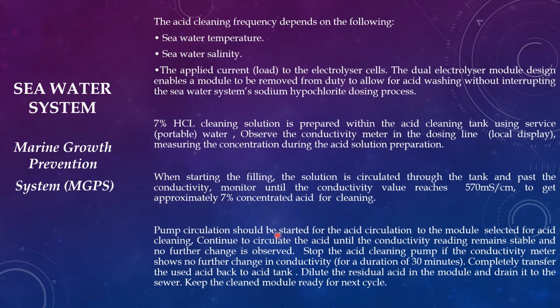Pump circulation should be started, and the 7% acid is ready for circulation to the module selected for acid cleaning. Continue to circulate the acid until the conductivity meter remains stable and no further changes are observed. When you start the circulation, conductivity starts increasing. When it remains stable, stop the acid cleaning pump. The conductivity meter shows no further change in conductivity for a minimum of 30 minutes. If it is stable and conductivity is not rising, then we can stop the acid cleaning.